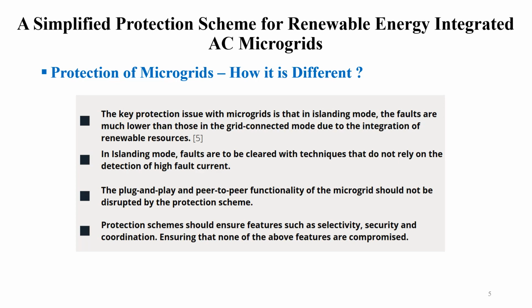The faults are much lower than those in the grid connected mode due to the integration of renewable energy sources. So what happens in an islanded mode is that if a microgrid is operating independently, the fault currents or the fault levels are much lower, because the power generated or the requirement is much lower compared to the big centralized grid. So again, in islanded mode, faults are to be cleared with techniques that do not rely on the detection of high fault current. Since the fault currents are not very high, the microgrid protection techniques do not require very high current fault detection techniques. Thus the plug and play and peer-to-peer functionality of the microgrid should not be disrupted by the protection scheme. This is again a very important aspect.